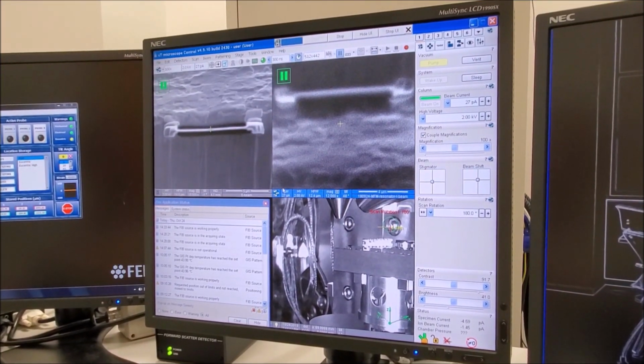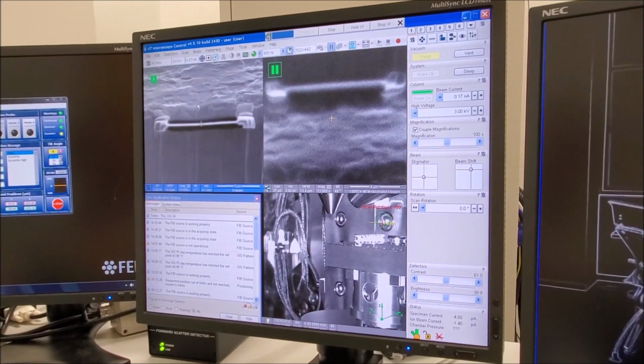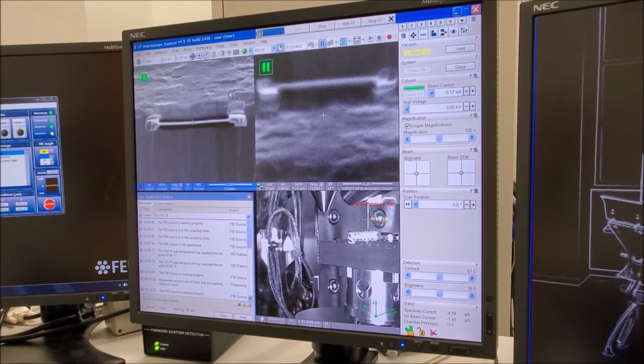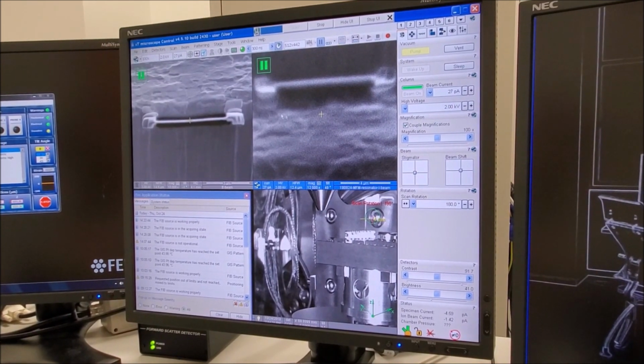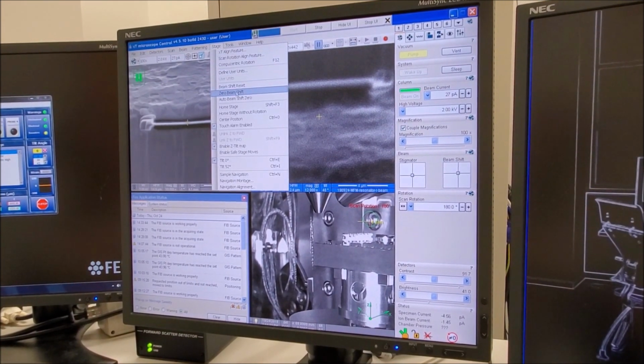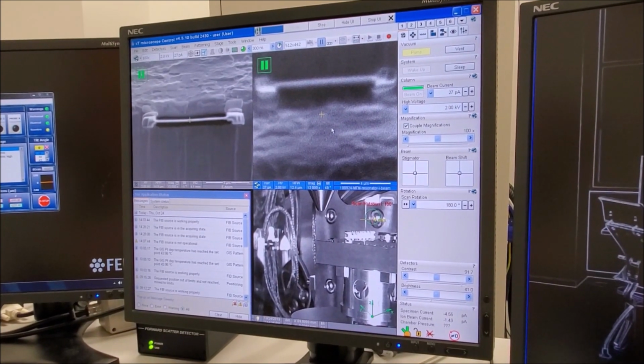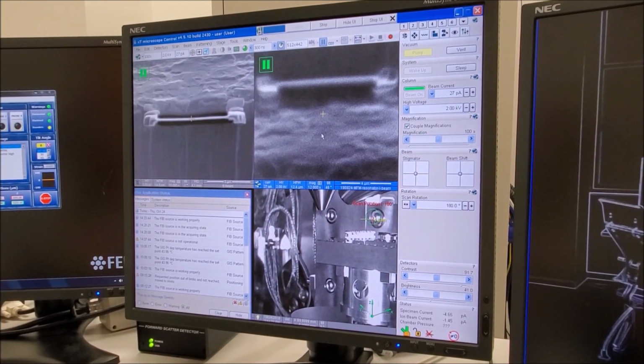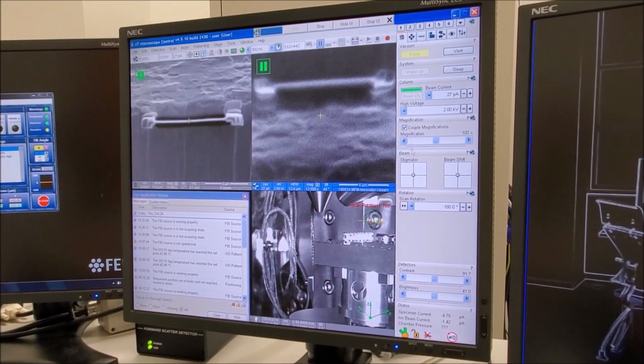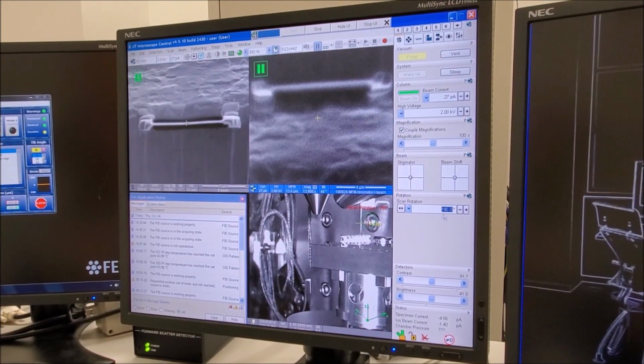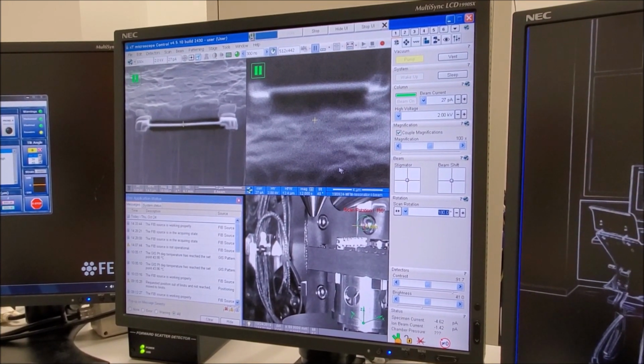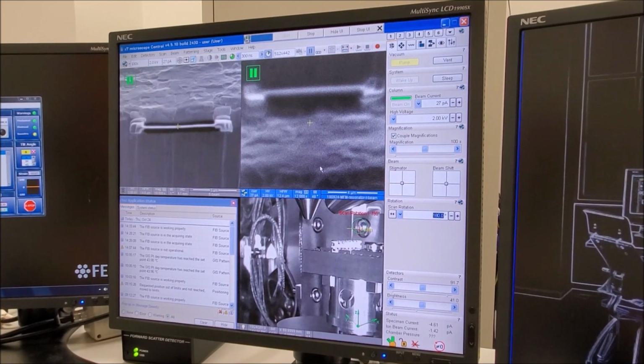While the chamber is pumping down, activate the electron beam quad and then select the stage pull-down menu. Then select 0 beam shift. Repeat this for the ion beam quad by activating it, going to the stage pull-down menu, and selecting 0 beam shift. With the ion beam quad still activated, remain in the beam control module and verify that the scan rotation is set to 180.